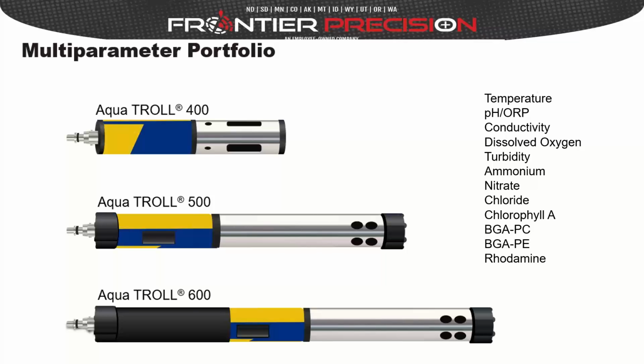On the Aqua TROLL 500 and 600, I use the comparison of a pizza, that you basically just build these up with the toppings of your choice. So you can say, okay, I want turbidity, dissolved oxygen, temperature, pH, and a central wiper on there. Or somebody may want a chlorophyll A sensor added to it. And with the 500 and 600 series, you also have the added option of a centrally located wiper that can be programmed to clean or sweep the sensors before every measurement is taken or at a timed interval that you would specify.